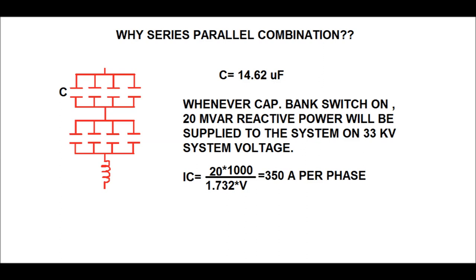If we use a single unit of value 2C = 29.24 microfarad, any failure in that unit would lead to complete shutdown of the capacitor bank. Also, whenever the capacitor bank is switched on in the 33 kV system, it supplies capacitive current to nullify the lagging reactive power in the system.